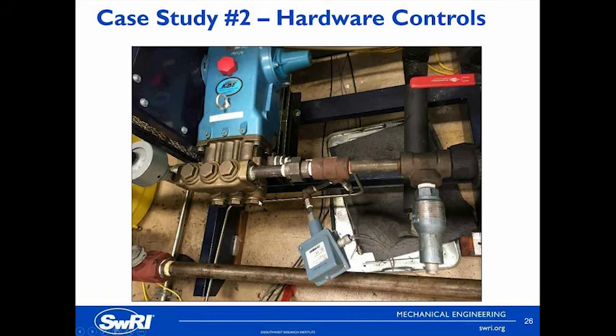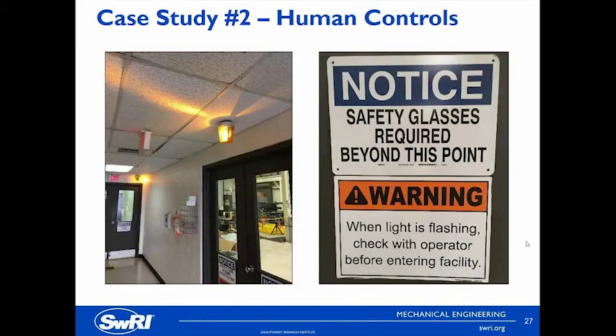This is a picture of the downstream of one of these triplex pumps. Since they are triplex pumps, they have the potential to overpressurize the facility quickly if there was a blockage — which is why just downstream there is a pressure switch connected to this pump. Then downstream of that there is a PSV that rejects fluid back into the separator. When you do that, you need to remember to design your PSV such that it opens at the required differential pressure. Since you may have up to around 100 PSI back pressure, the PSV needs to be sized so that it overcomes the differential pressure required. That's an easy way to accidentally undersize a PSV. On the outside of this test facility, we have signage and lights to let operators or non-operators know what's going on inside the facility.